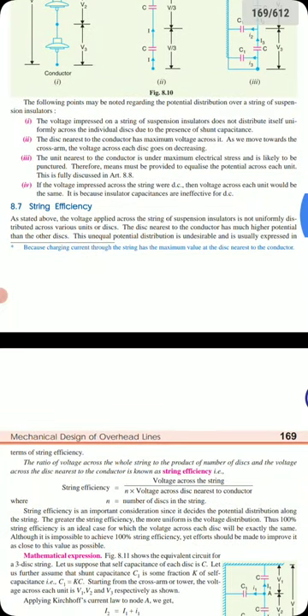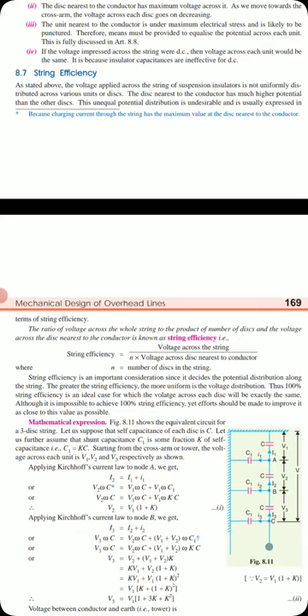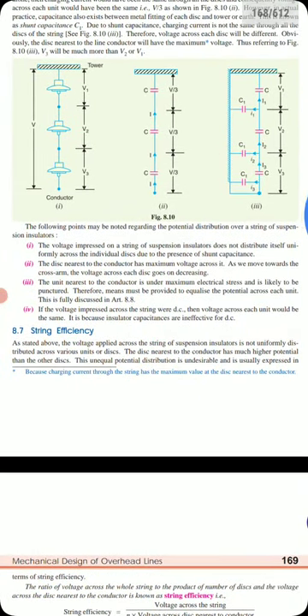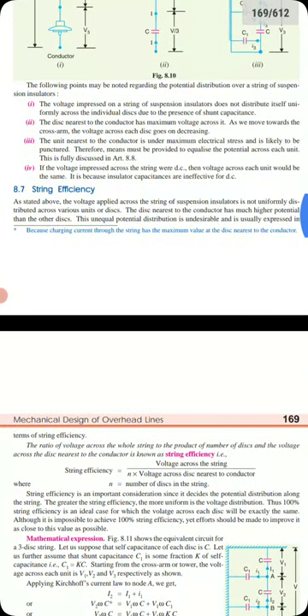String efficiency is defined as the ratio of the voltage across the whole string to the product of the number of disks and the voltage across the disk nearest to the conductor. The string efficiency formula is: V divided by (n × V3), where V is the total voltage across the string, n is the number of disks, and V3 is the voltage across the disk nearest to the conductor.